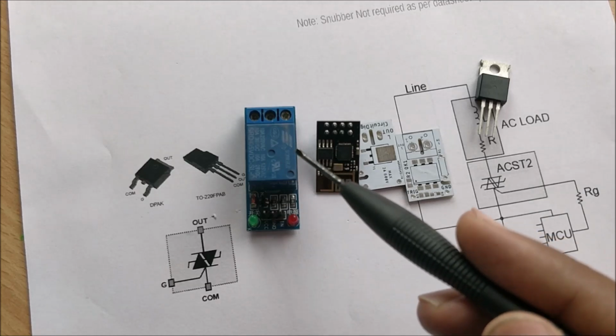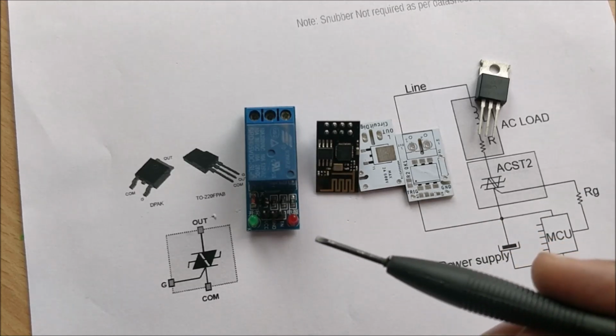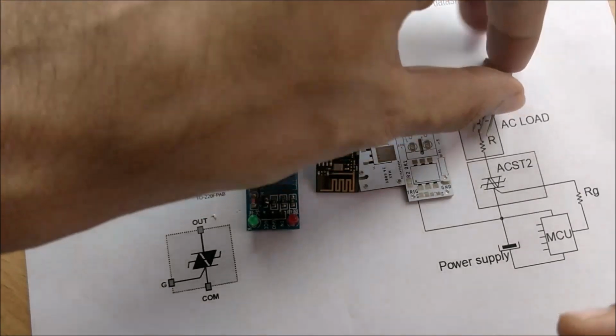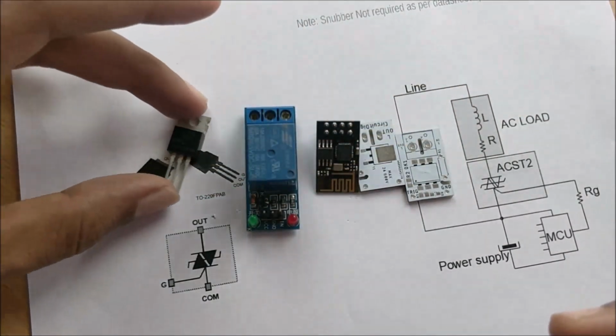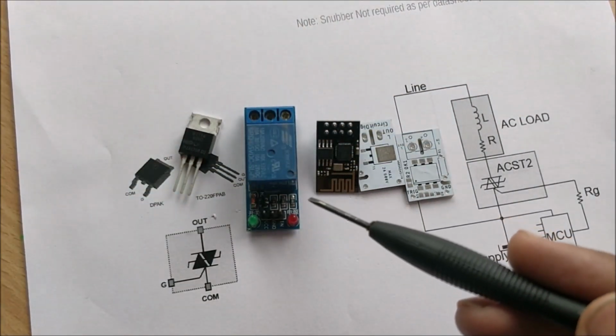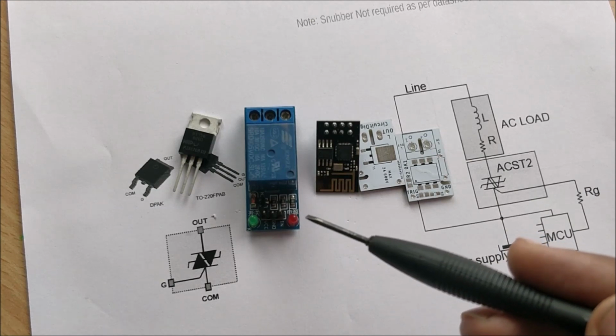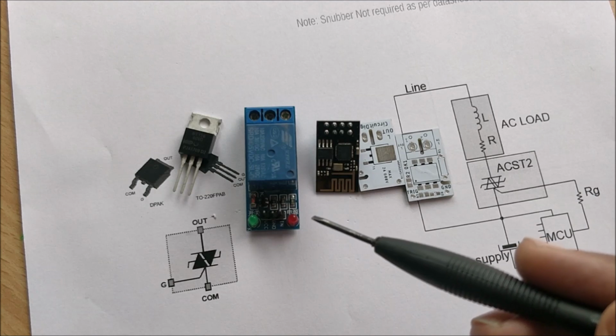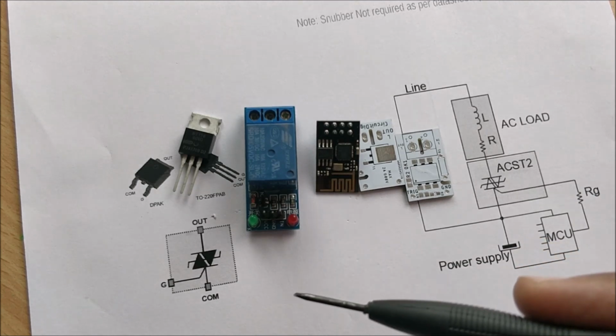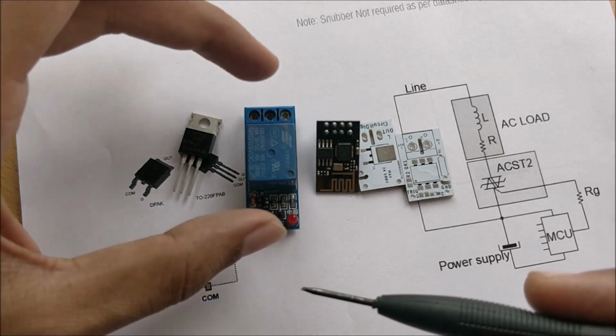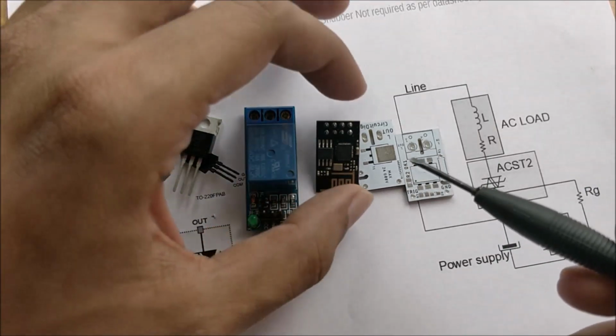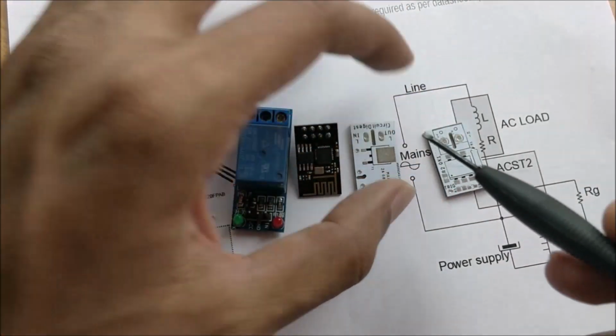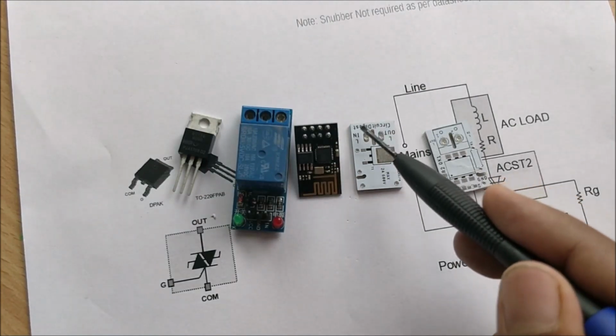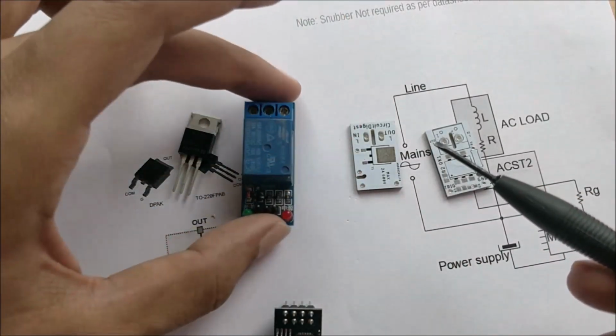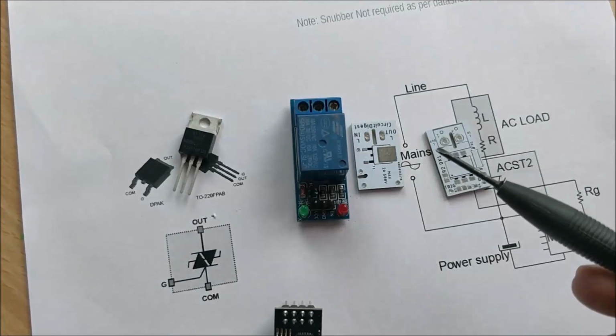And the second thing is, electromechanical relays tend to consume more power than your solid state devices like a TRIAC or an SCR. And the third thing is, electromechanical relays tend to wear off in time because of the mechanical operations inside, and the lifespan is comparatively less compared to a solid state relay. And another thing is that they are bigger than your solid state relay. So if you can see here, a complete solid state relay board is only going to be of this size, but when you compare it with an electromechanical relay, it's quite big.